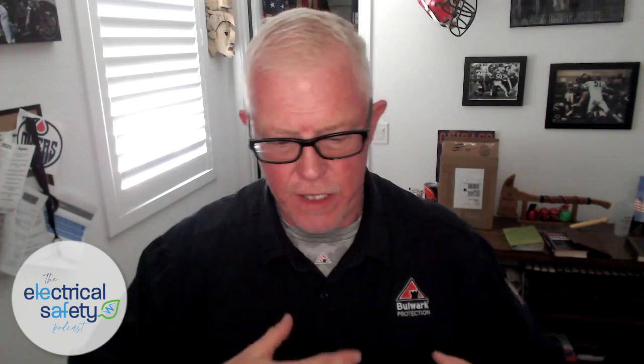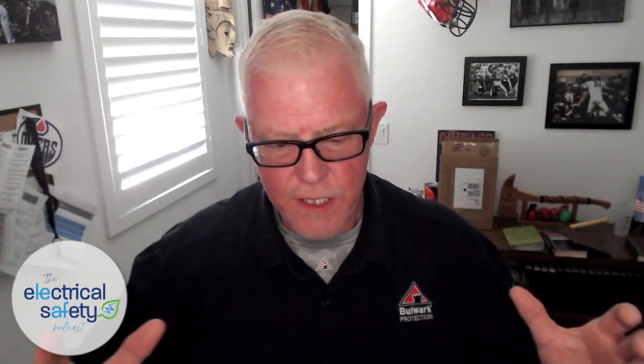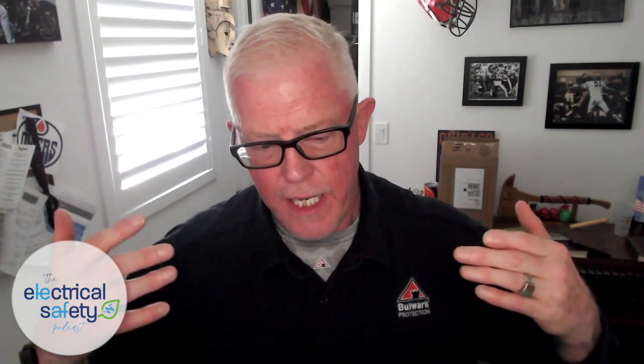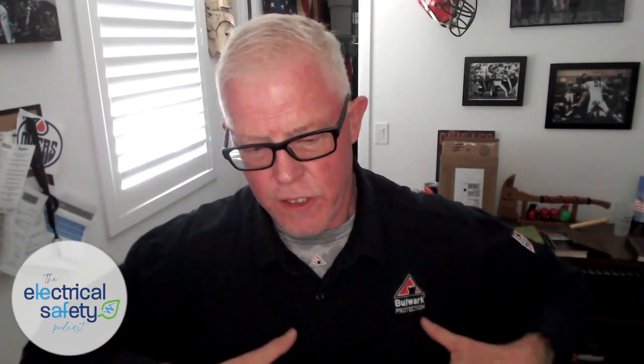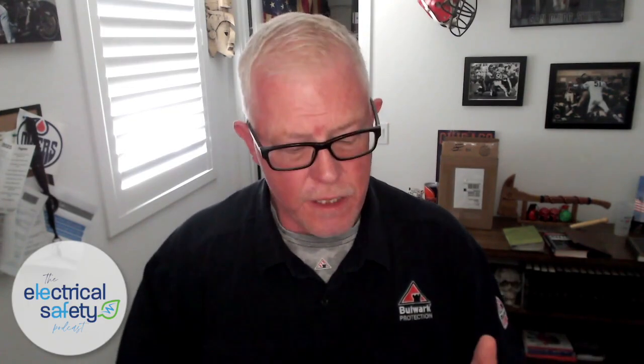I potentially could have more injury, more second-degree burn than I would have if everything happened according to exact distance and exact incident energy, 5 calories of energy, 8 calories served perfectly. Got a little closer, lasted a little bit longer. I'm now at 18 to 20 calories of energy. I've started to break open. I am going to have a section of my torso and/or arm potentially receive second-degree burns that I may not have originally. The good thing is those second-degree burns will still heal up on their own. We've still mitigated catastrophic, potentially fatal injury.